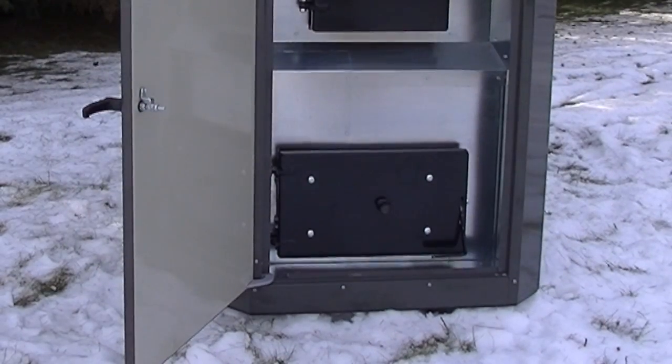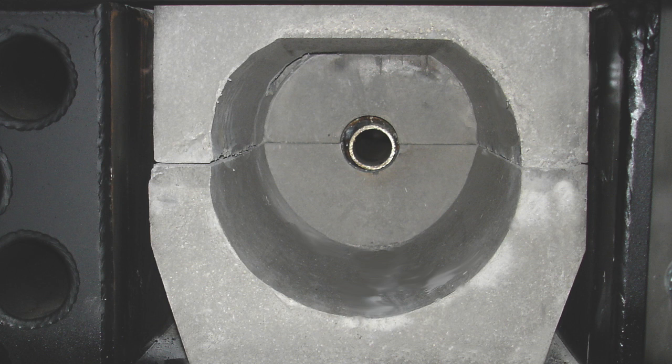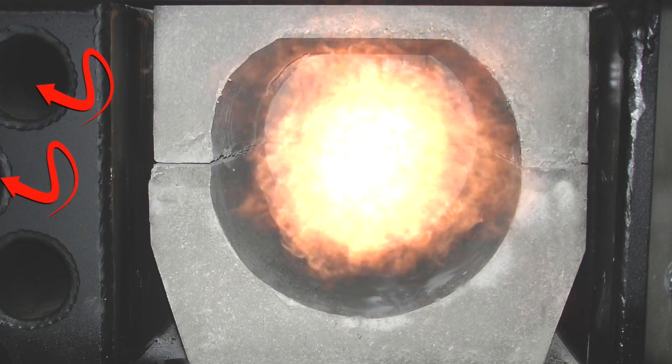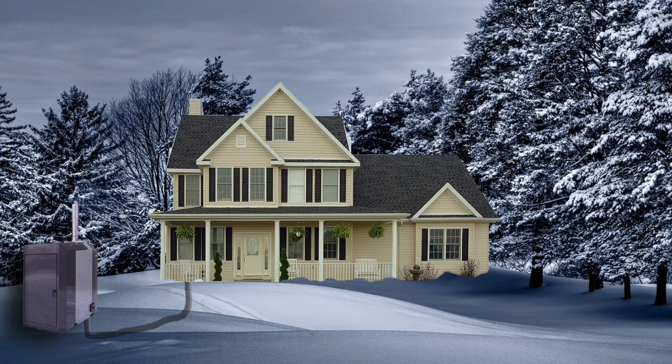Stepping back for a second and having another look at the front of the EGR, you will notice the second hinged latchable door with a small inspection glass port in the front of it. Opening this door reveals that it is covered in refractory cement, as is the refractory-constructed reaction chamber with its extra heavy-duty offset chamber nozzle. This nozzle is designed for optimal turbulence and causes the superheated fire to swirl around inside the reaction chamber before exiting out through the lower horizontal and rear vertical heat exchanger tubes. Both the horizontal and vertical heat exchanger tubes run straight through the upper and lower water jackets before exiting through the chimney, depositing all of their stored heat into the water. This water is then pumped into your home where it can be distributed into all of the rooms via a forced air furnace, in-floor heating, or even the old-style cast iron radiators.